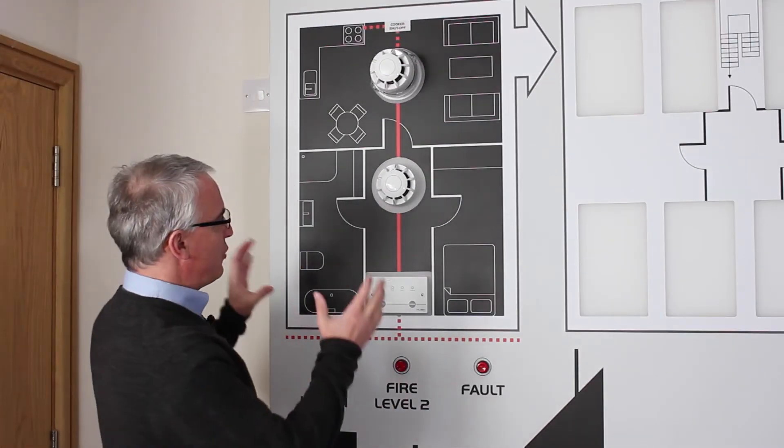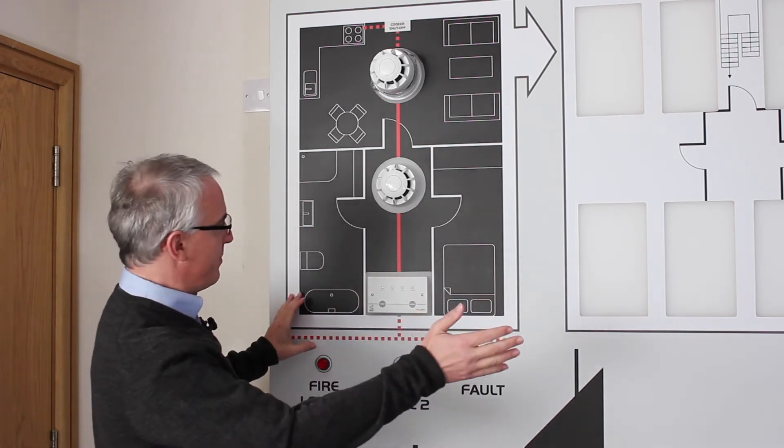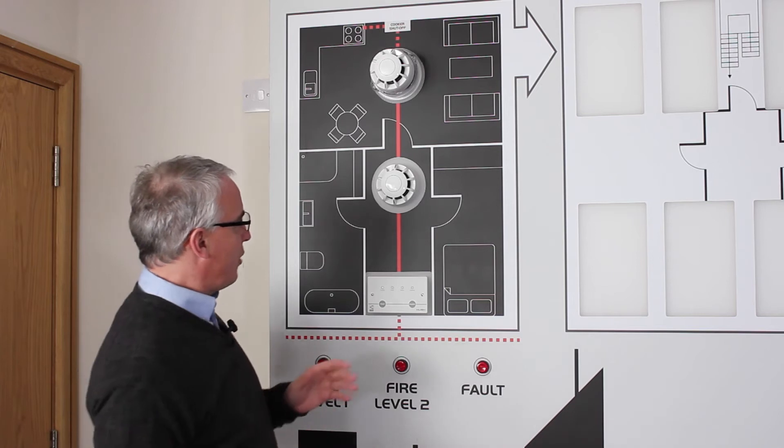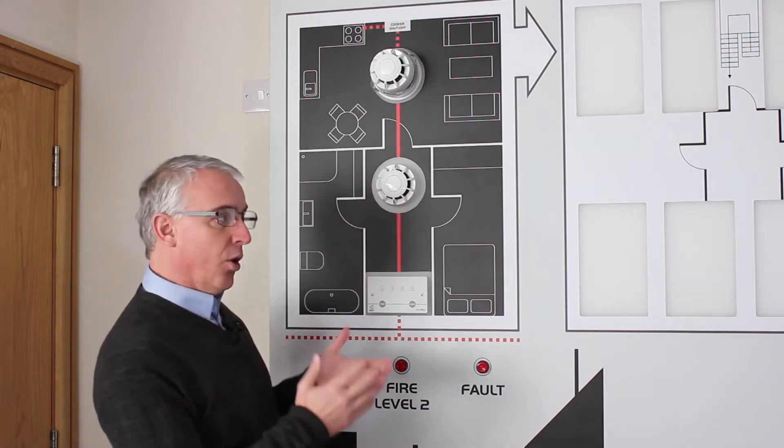Okay, so the individual dwelling, as we have said, is connected to the landlord monitoring panel. Now should a fault occur in the dwelling, maybe because somebody's removed a detector head or the wiring has been damaged, the fault when it happens will flag at the Hush controller.